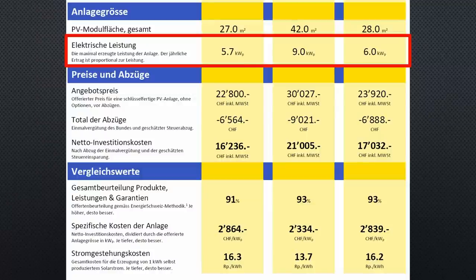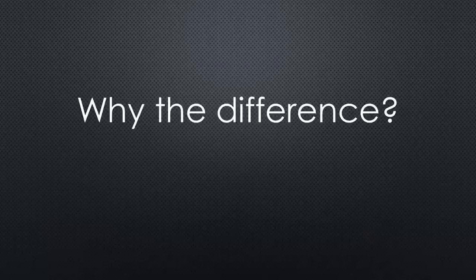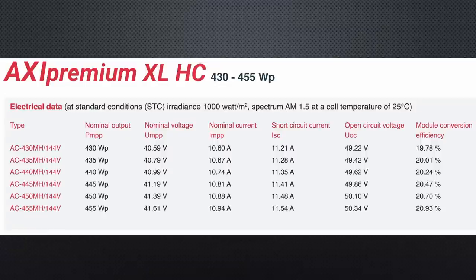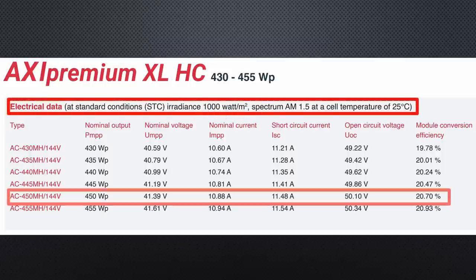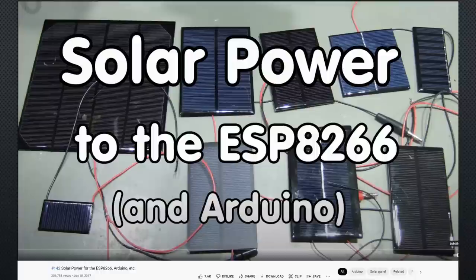Here is the overview of the three offers from a technical perspective. Two suppliers offer around 6 kW peak and one offers 9 kW peak. kW peak is the maximum power a solar panel can produce. Here is the datasheet of a typical module: the nominal output power at 1000 W per square meter solar irradiance is 450 W at 41.39 V and 10.88 A. If open, the module delivers 50.1 V, and if shorted, it delivers 11.48 A.